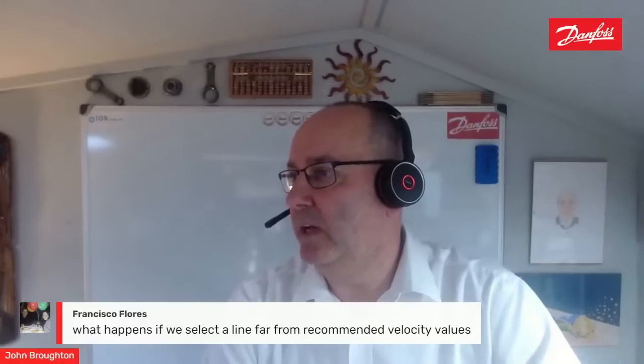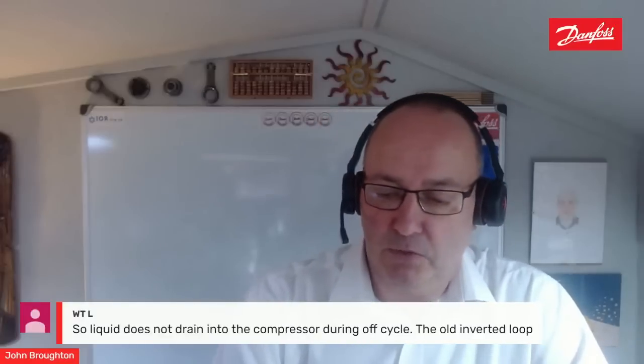And Warren comes back. So he says, if the condenser unit is above the evaporator, use an inverted loop at the outlet of the evaporator that rises above the evaporator, correct? So the liquid does not drain into the compressor during off cycle, the old inverted loop. Yeah, I sort of call them swan necks and goosenecks.